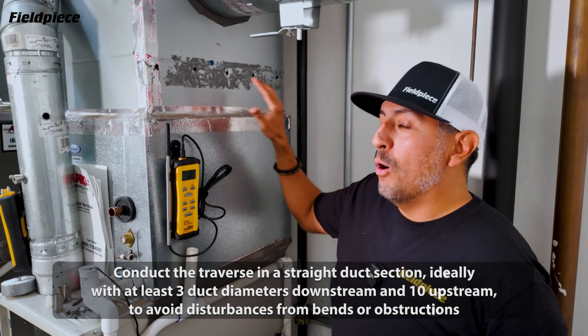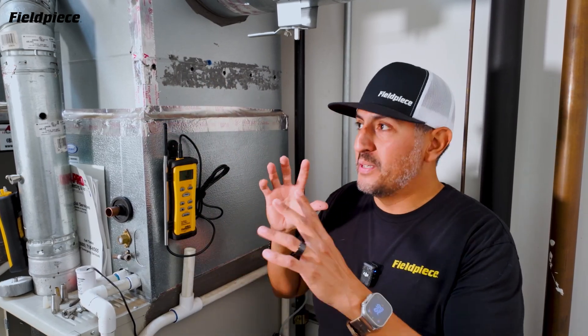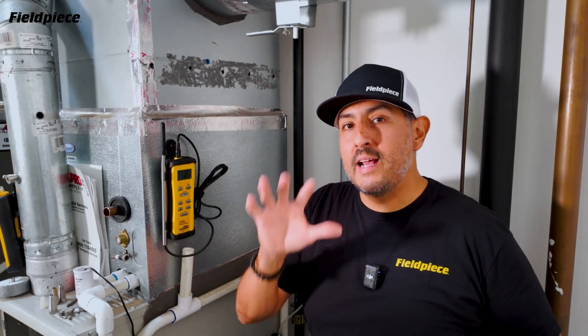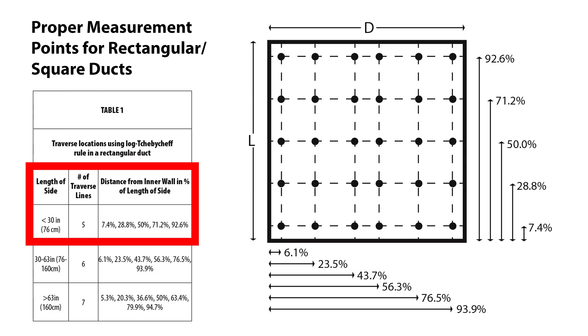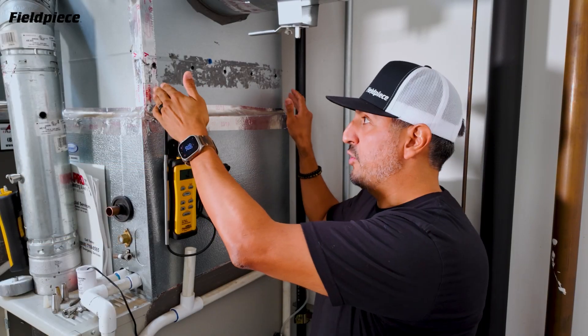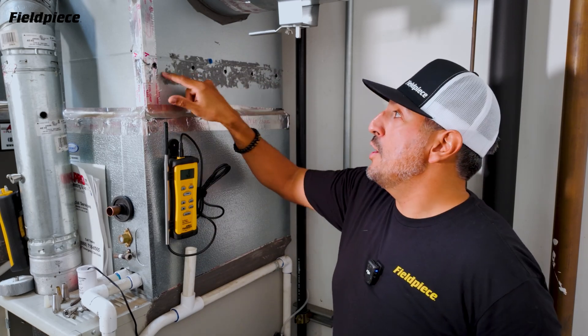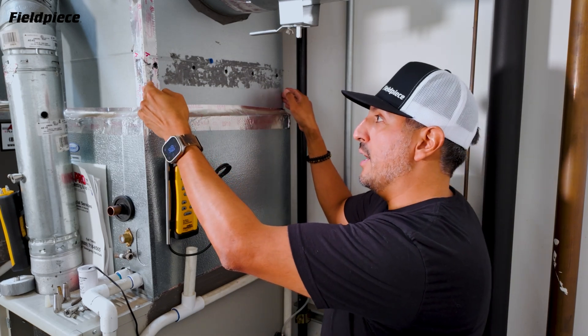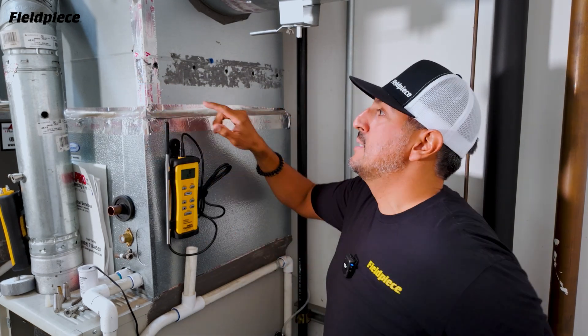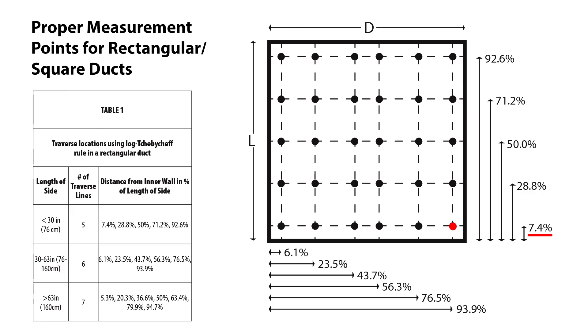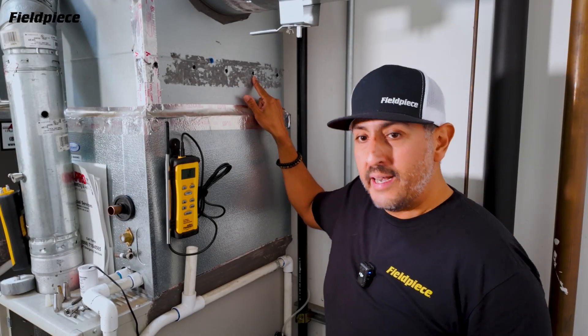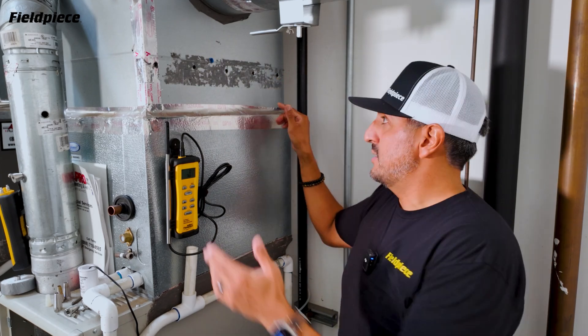Now how many holes you drill into your duct and where you position those holes is important. For a duct that is less than 30 inches, industry says we need five holes. Any duct from 30 to 60 inches, you need six holes. We have a 20 and a quarter inch width duct here so I have five holes. Based on industry tables, your first hole is drilled at 7.4% of the duct width, the next at 28.8%, the third at 50%, the fourth at 71.2%, and the last at 92.6%.